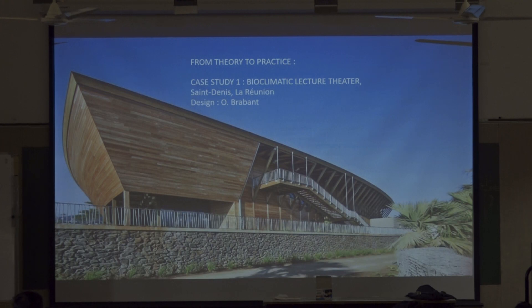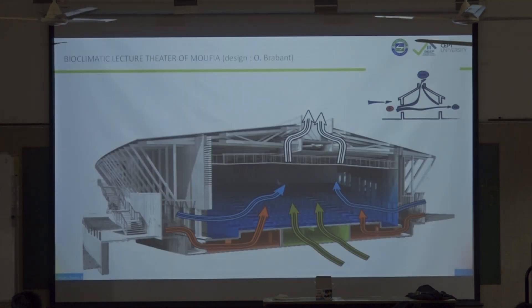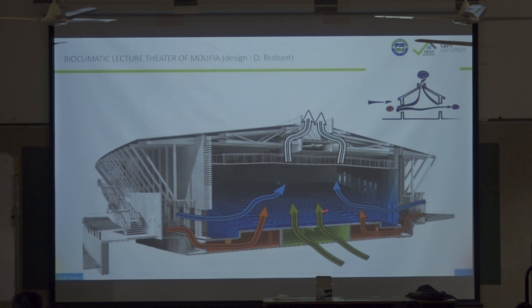Case study: the bioclimatic lecture theater I presented two days ago — I will now focus more on natural ventilation. The building is a light structure in wood. The principle: we created a low pressure shaft in a U-shape of 3 by 3 meters. The wind is accelerated there — this is the natural pump. We have louvers on each side; the total distance is 30 meters, more than the 10-meter threshold, which is why natural cross ventilation alone doesn't work here.